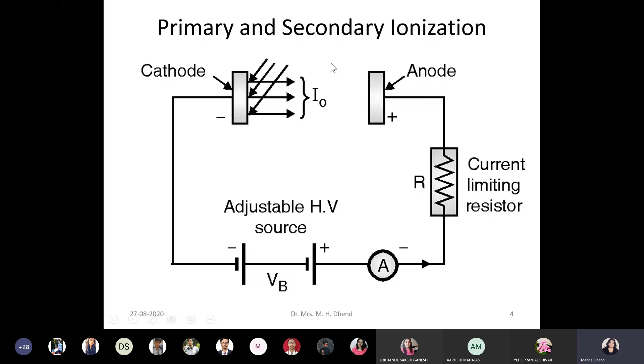Factors affecting breakdown we have discussed: applied field, gap separation, cathode work function, temperature of cathode, size and shape of electrode, material of electrode, thickness and density of materials. Because if you are testing air, you will get a different voltage. If you are testing liquid, you get a different voltage. Applied voltage waveform is also important. Frequency is also important. Rate of change of voltage is also important. So read this.